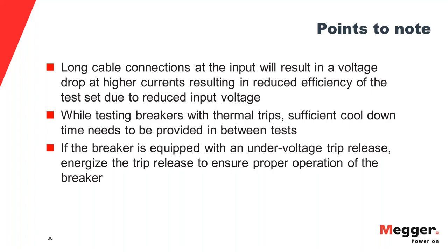And if that high current flows on the input side through really long cables, then there will be a voltage drop, which will result in lower input voltage on the test set. Lower input voltage means reduced output from the test set. So that's something that you need to take note of to make sure that the cables are only as long as they need to be, and they are the right size, of course.